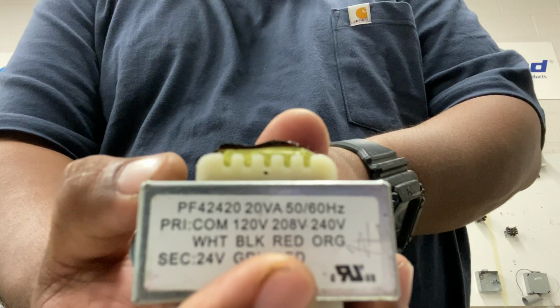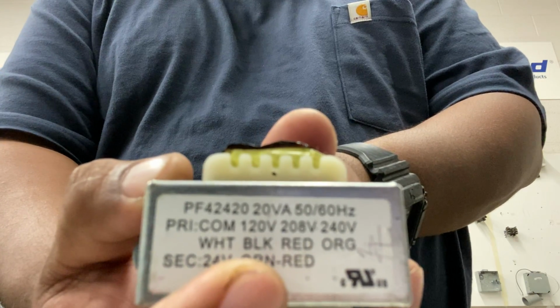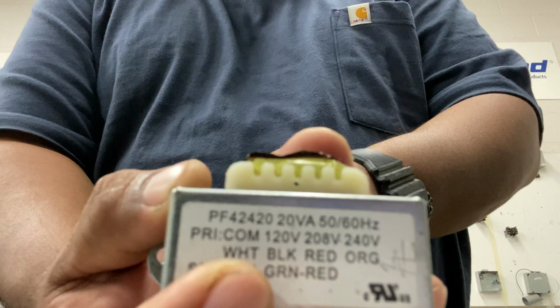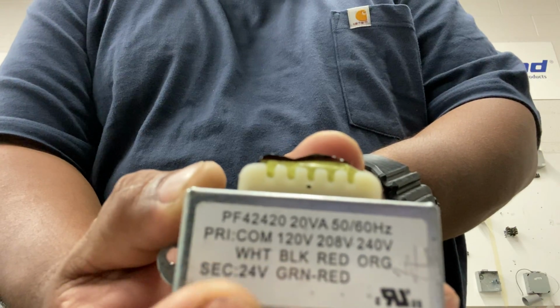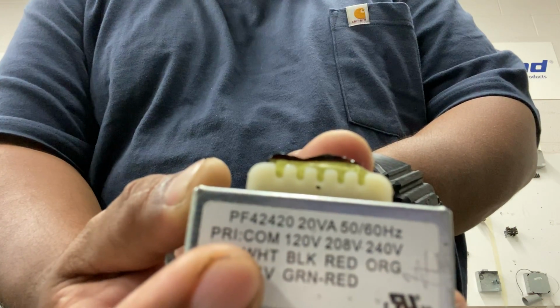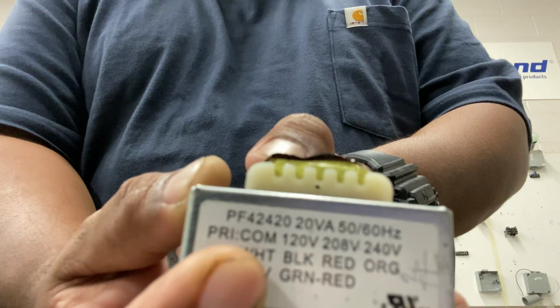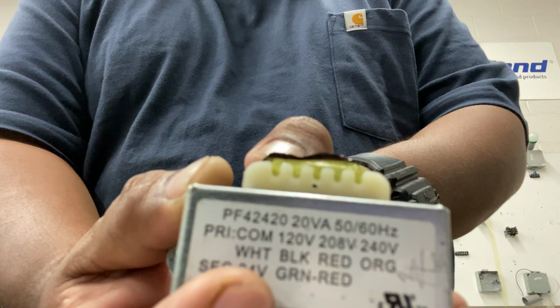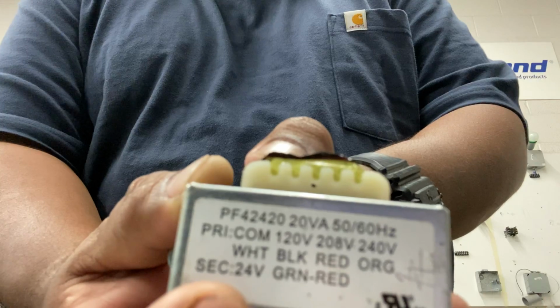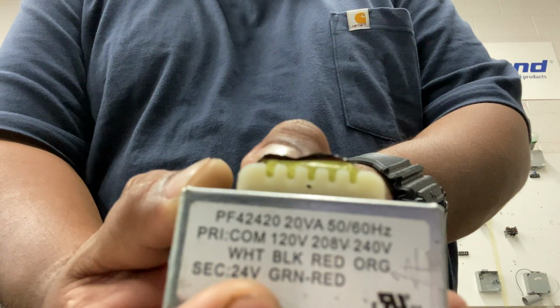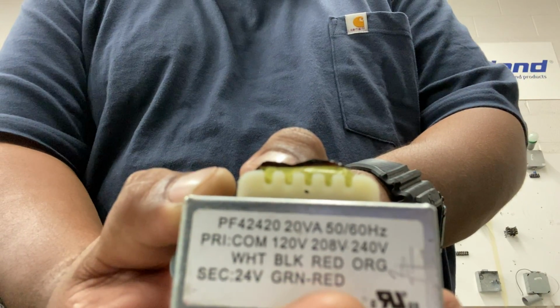208 is going to be hooked up to red. 120 volts is going to be hooked up to black, and then common is going to be hooked up to white. Right? You see here it says pri or pre. That's the primary winding it's talking about. Then down here at the bottom, this will be your secondaries. Secondary 24 volt voltage, green and red.